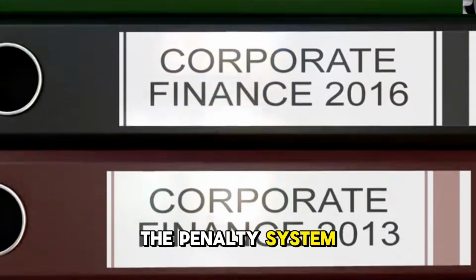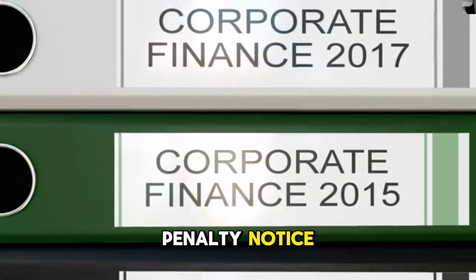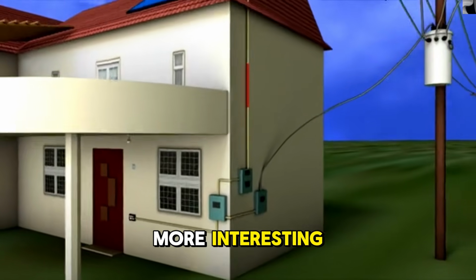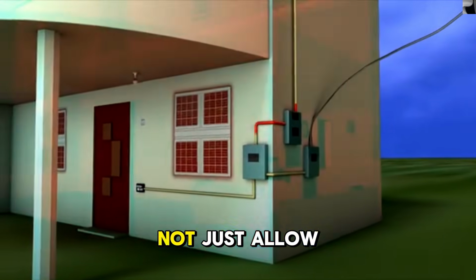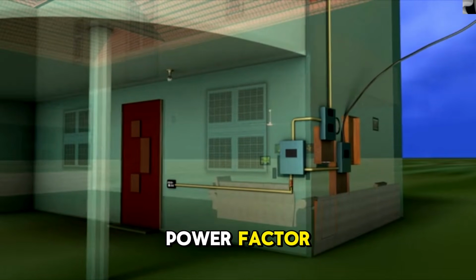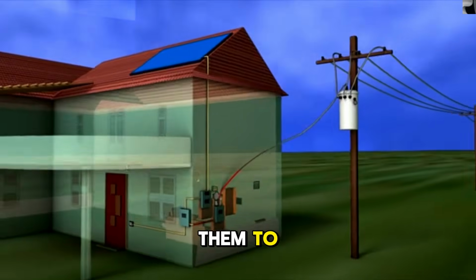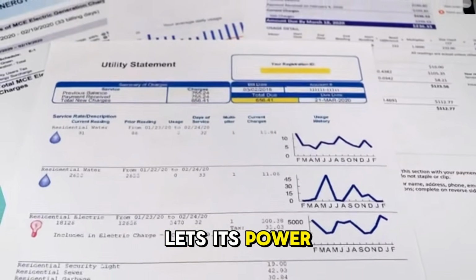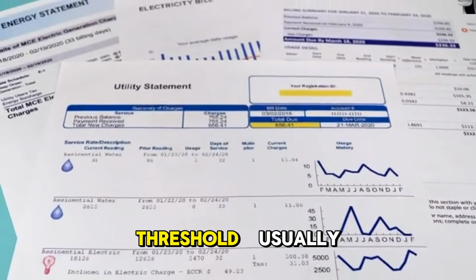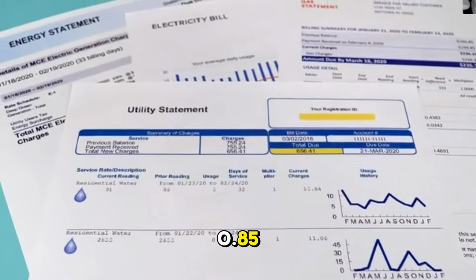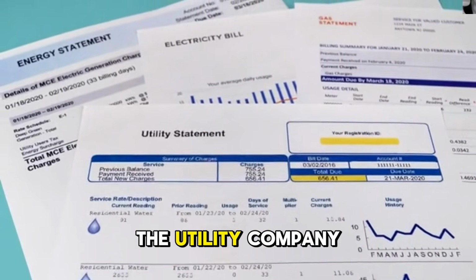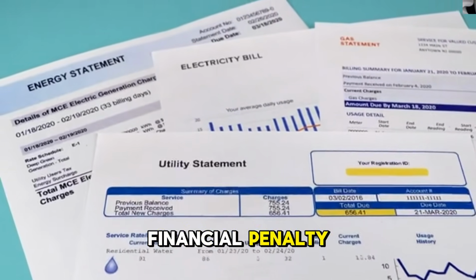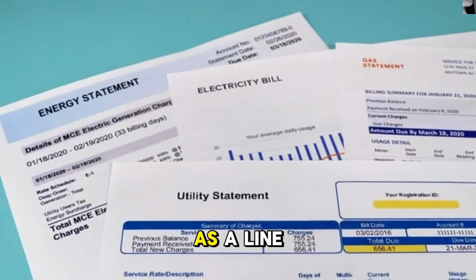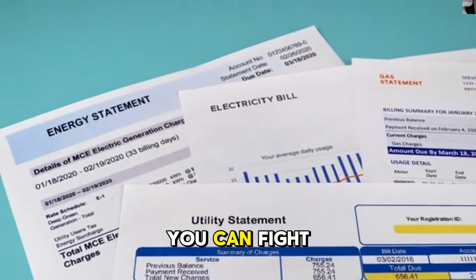The penalty system. Here's where it gets even more interesting. Utility companies do not just allow factories to fix their power factor, they actually force them to. If a large industrial facility lets its power factor drop below a certain threshold, usually 0.85 or 0.90, the utility company slaps them with a direct financial penalty on their bill. It shows up as a line item. You can see it. You can fight it.